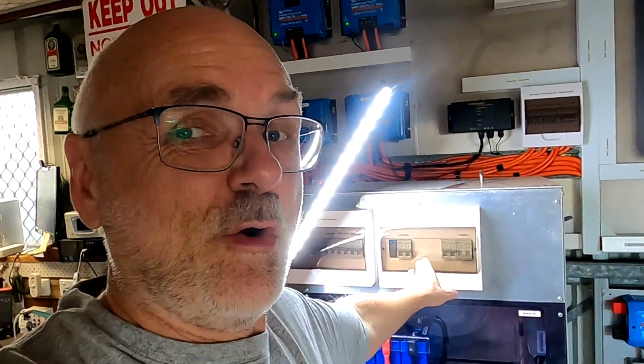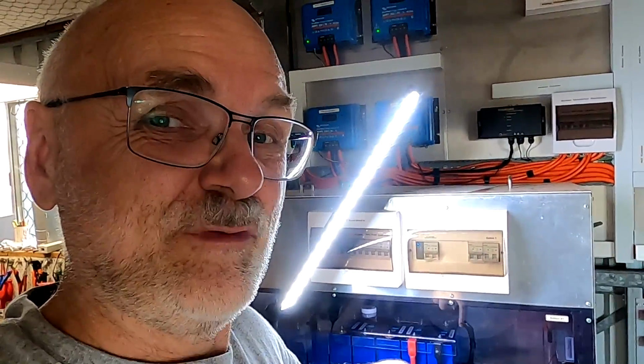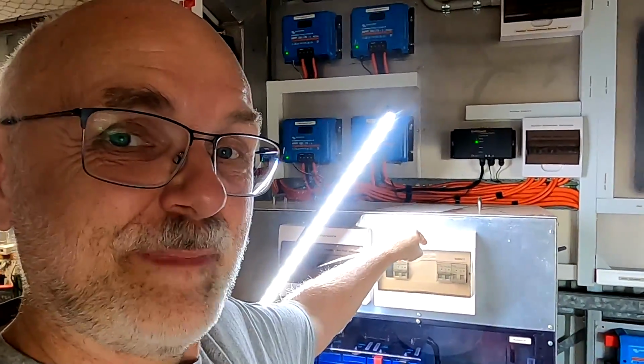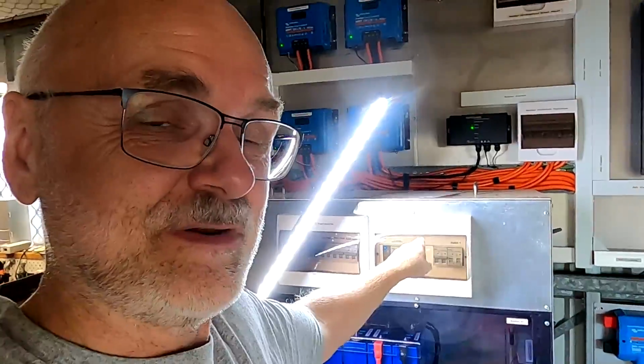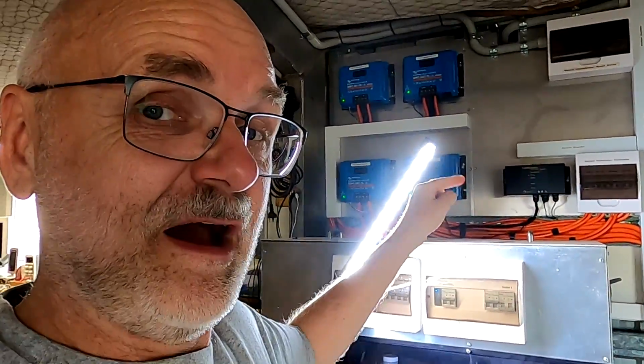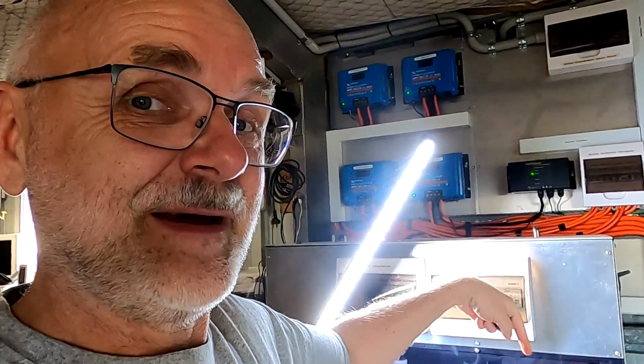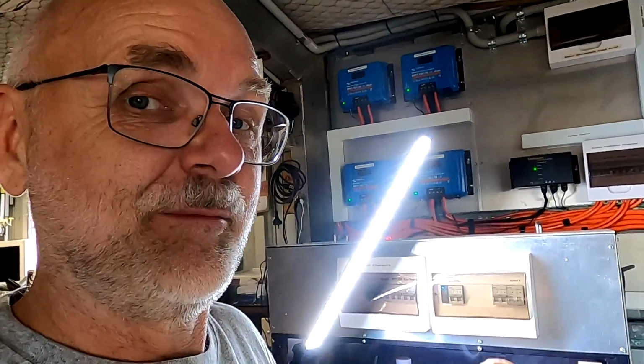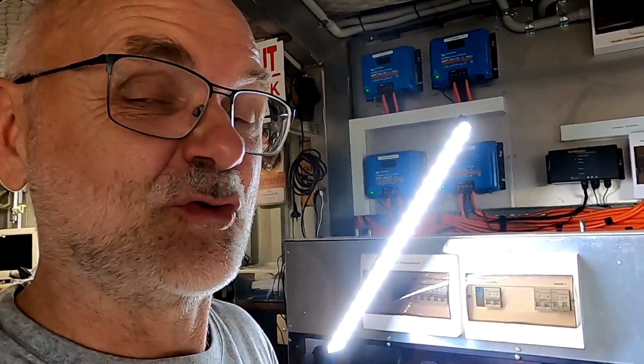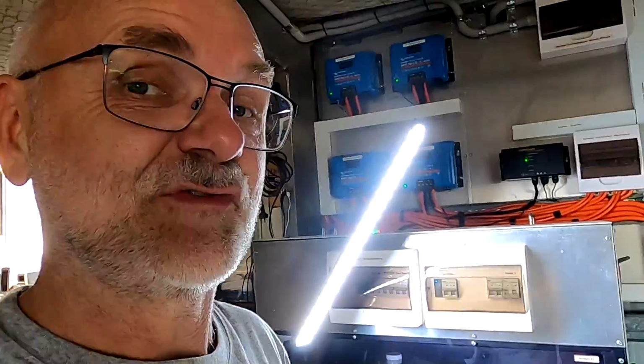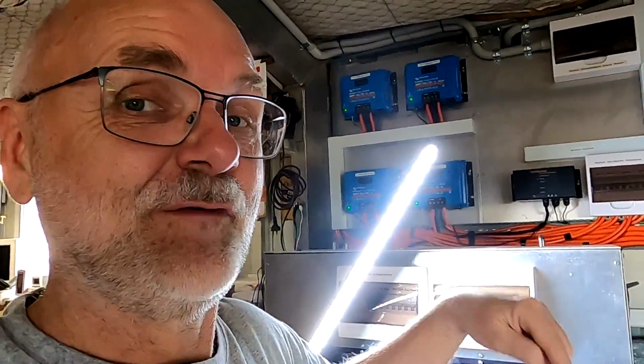So even though the DC load is not connected directly to our battery here, it is connected to the main bus bar system in the top battery compartment. So power coming from the solar going out of this outlet number 1 is not being counted for by the smart shunt. Usually you don't connect batteries to this outlet because the battery needs to be on the other side of the smart shunt.